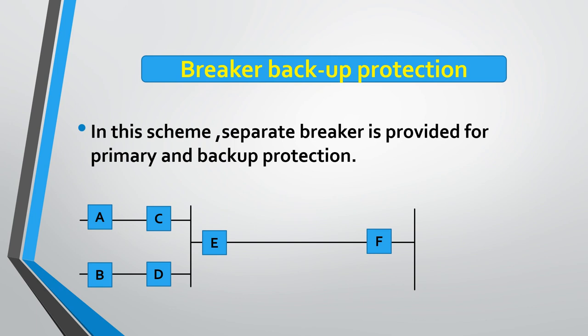In breaker backup protection, a separate breaker is provided for primary and backup protection. For example, if a bus bar is protected by circuit breakers C, D, and E, and any of these fails to operate, then circuit breaker A or B will give protection to that bus bar. This is how the bus bar gets protected by breaker backup protection.